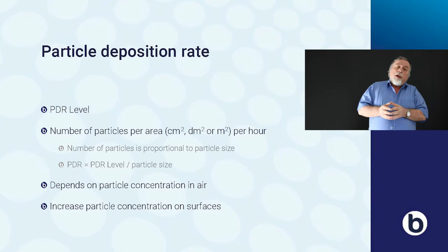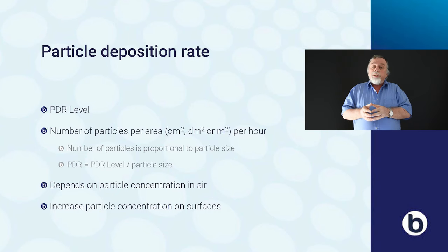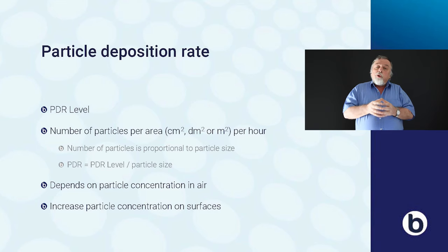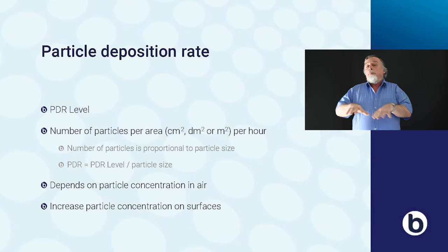Particle deposition depends on the particle concentration in air. Particle deposition will also cause an increase of particles on surfaces and thereby impact surface cleanliness. Particle deposition rate is the product of particle concentration in air times the deposition velocity. Particle deposition rate is also equal to the change of surface cleanliness divided by time.